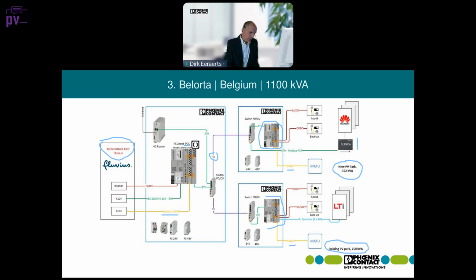An extra functionality that we added in this case is that since the old plant receives higher subsidies or a higher feed-in tariff, when we receive a control signal from the DSO, we will first of all reduce the new part of the plant, because we have less financial losses by doing that, and only if that is not sufficient will we switch also to the old plant and reduce that further.